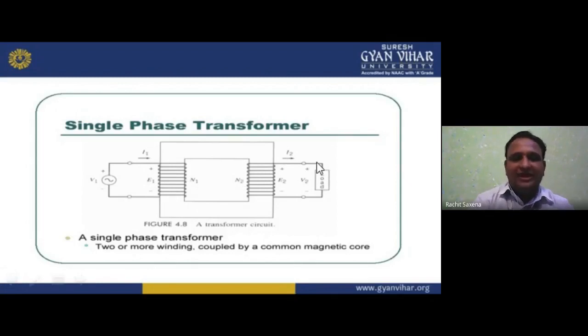So in a single phase transformer, the windings are magnetically coupled because of the common core, but electrically separated. Magnetically coupled and electrically separated. Why is it so? Because we are giving electrical supply to the primary side and taking out the supply from the secondary side, that is, we are connecting the load. So, two or more windings coupled by a common magnetic core.